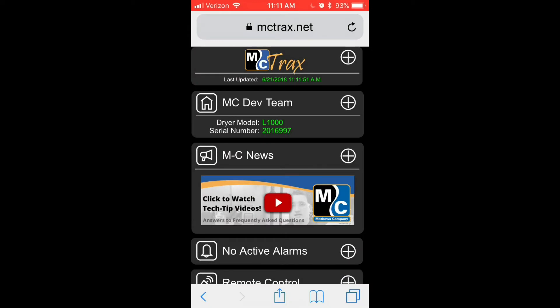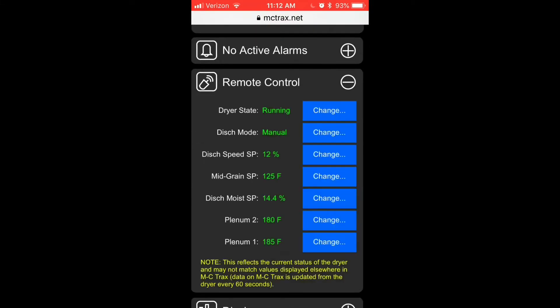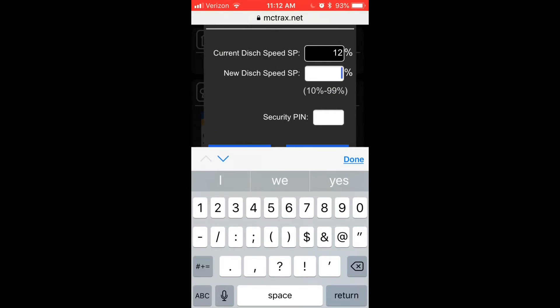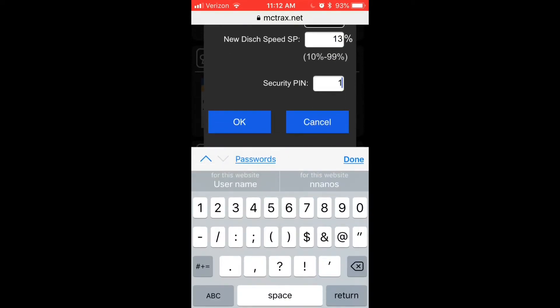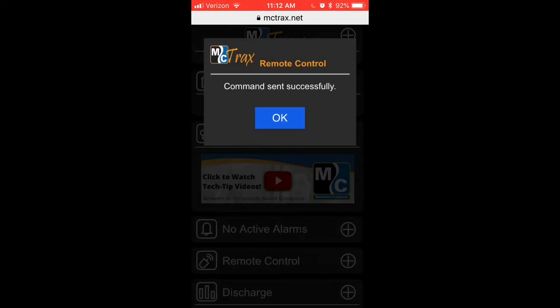Once I've enabled remote access from the HMI, I can log back into MC Trax. If I open the remote control panel, I'll see that I now have the ability to make changes to several key set points. For instance, if I'd like to change my discharge speed set point, I'll click the blue Change button, enter my new desired set point, and then enter my four-digit security pin. I'll hit OK, I'll be prompted one more time to send my command, and within a few seconds I'll get a message that tells me the command was sent successfully.